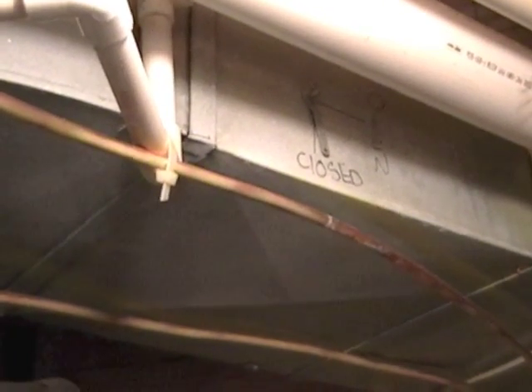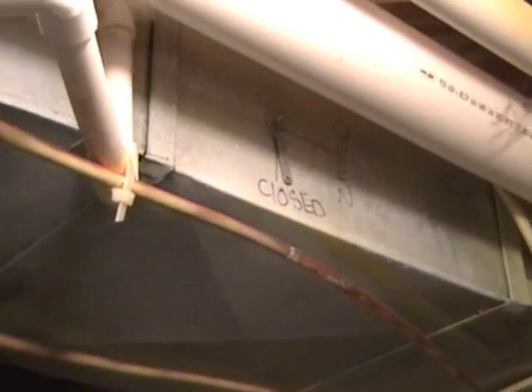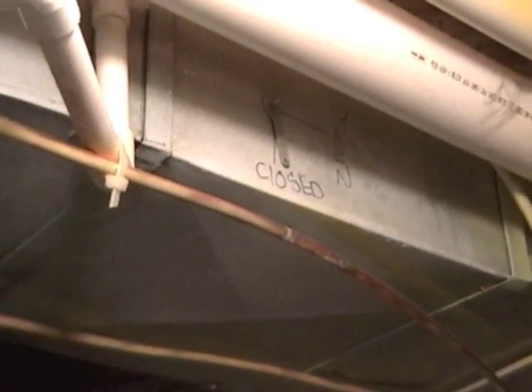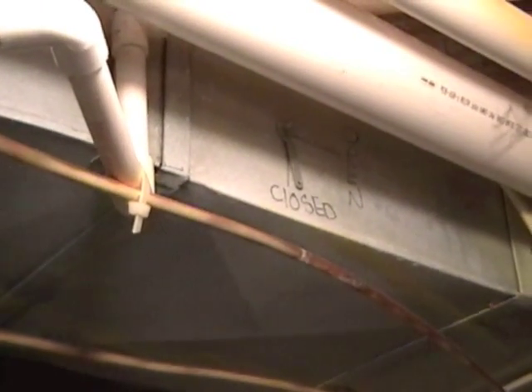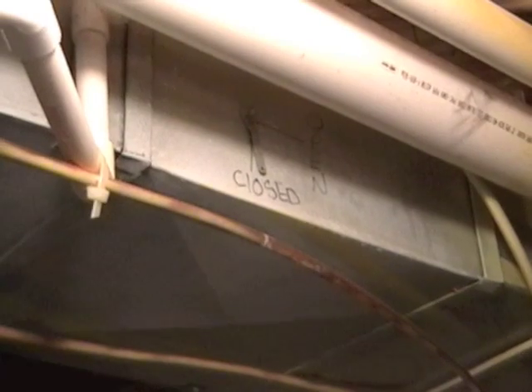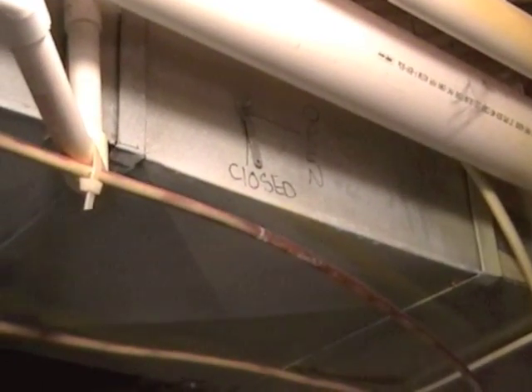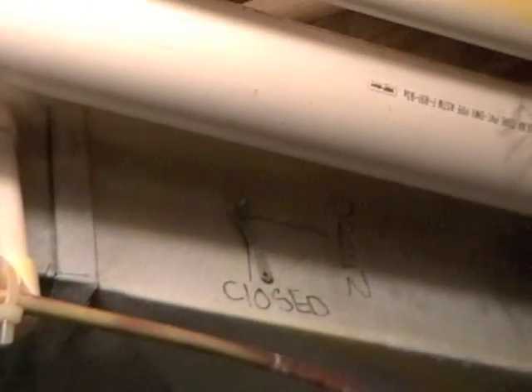To start, you need to find out where the damper is in relation to the ductwork. In this case, the ductwork for the damper is connected to the ductwork that services the lower level. In this case, that's the bathroom here, and the main levels. This line has pipes that go into the main level of the townhouse. Here we're going to almost close, as you see now. This is for letting less air in the main and the lower levels, and in turn will allow more air to go to the top floor.